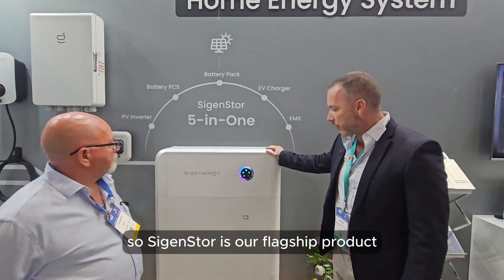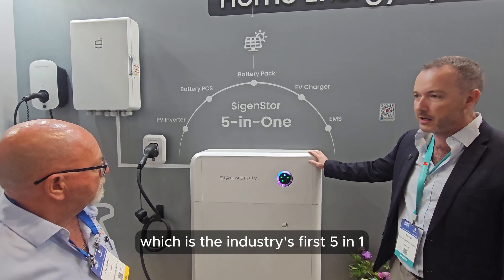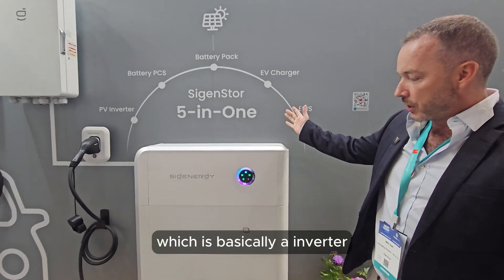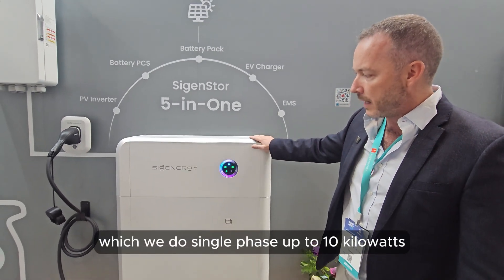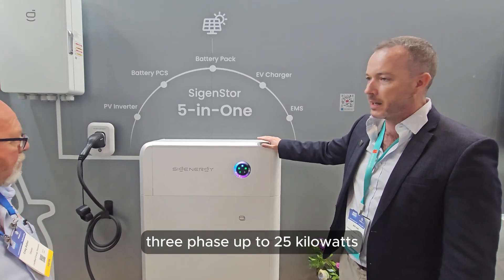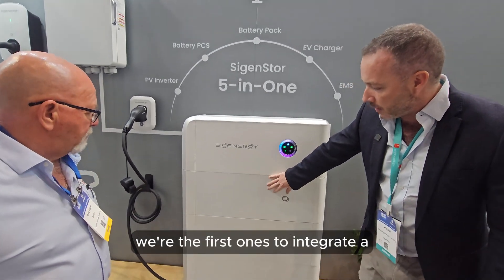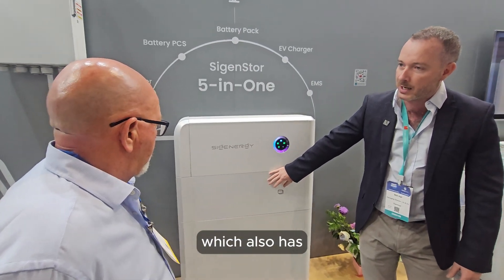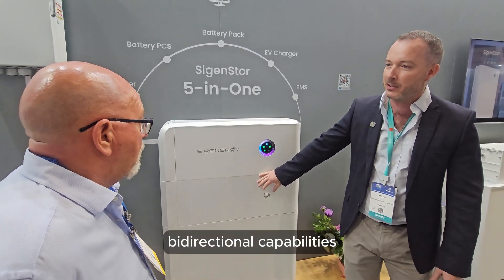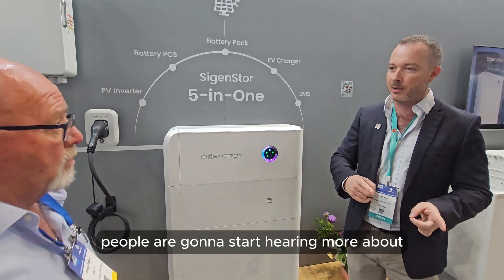SigenStor is our flagship product, which is the industry's first five-in-one energy storage system. It's basically a hybrid inverter - single phase up to 10 kilowatts, three phase up to 25 kilowatts. We're the first ones to integrate a 25 kilowatt DC fast charger, which also has bi-directional capabilities - vehicle to home and vehicle to grid - which people are going to start hearing more about fairly soon.